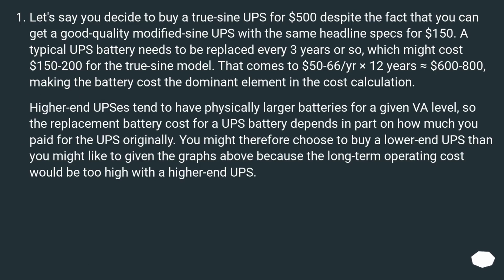Let's say you decide to buy a true sine UPS for $500 despite the fact that you can get a good quality modified sine UPS with the same headline specs for $150. A typical UPS battery needs to be replaced every 3 years or so, which might cost $150 to $200 for the true sine model. That comes to $50 to $66 a year, or $600 to $800 over 12 years, making the battery cost the dominant element in the cost calculation.